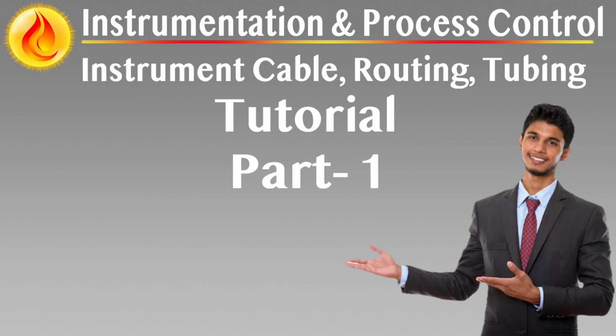Signal integrity depends on solid insulated conductors, minimum diameters 1.13 millimeters for singles, 0.8 millimeters for multi-cores, and accurate voltage drop calculations. Signal wiring from field devices to junction boxes uses single cables, while multi-core cabling conveys signals to central or auxiliary control rooms. Underground routing is preferred for multi-core runs due to its superior protection against fire and mechanical damage. Above-ground runs are acceptable if justified economically and approved by the principal.